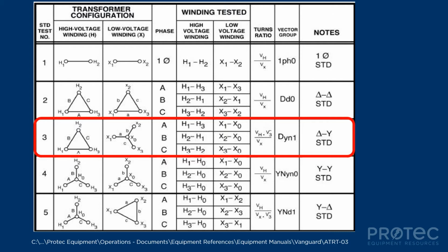If you have any questions about what's shown on this, you can find this table pretty much in any of the test equipment manufacturers' materials that supply transformer turns ratio test sets. There's a path labeled at the bottom of the screen where the folks from Protec can go and look at what's been pulled out of one of the manufacturers' instruction manuals. It's several sheets. One manufacturer, if I'm not mistaken, actually has laminated cards that go in the sleeve of the cover of the test set. So they're readily available. You don't have to remember all of this stuff.